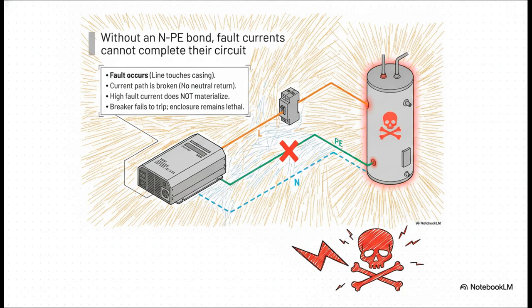Because there's no neutral return path to complete the circuit, very little fault current flows. And guess what? The breaker completely fails to trip. That water heater enclosure just sits there, dangerously energized, and remains entirely lethal to anyone who touches it. It's a terrifying thought, right?